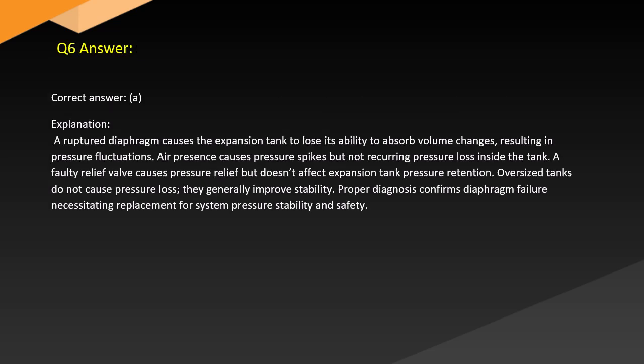Answer. Correct answer, A. Explanation. A ruptured diaphragm causes the expansion tank to lose its ability to absorb volume changes, resulting in pressure fluctuations. Air presence causes pressure spikes, but not recurring pressure loss inside the tank. A faulty relief valve causes pressure relief, but doesn't affect expansion tank pressure retention. Oversized tanks do not cause pressure loss, and they generally improve stability. Proper diagnosis confirms diaphragm failure, necessitating replacement for system pressure stability and safety.